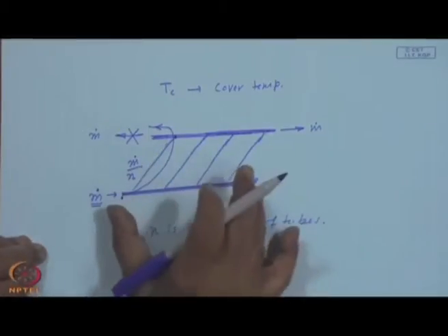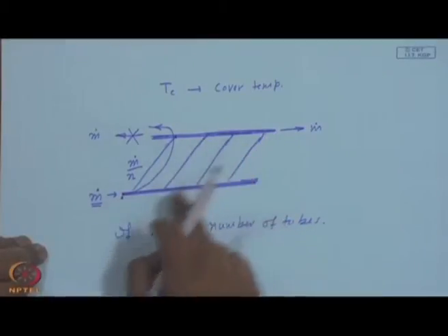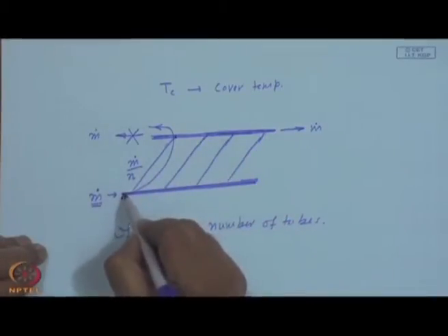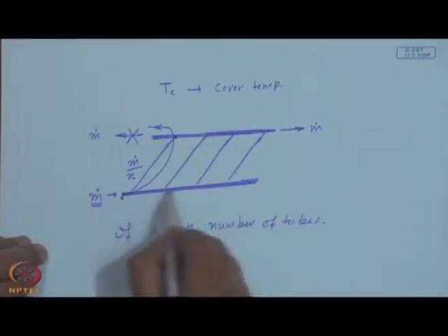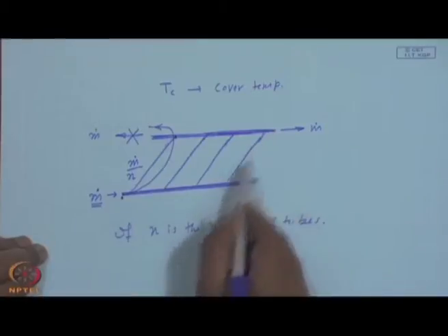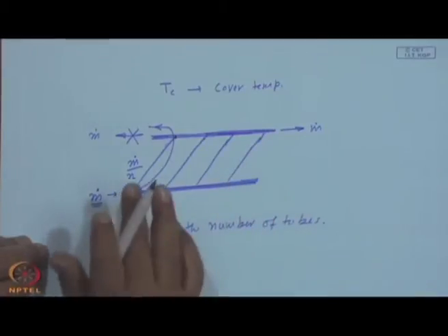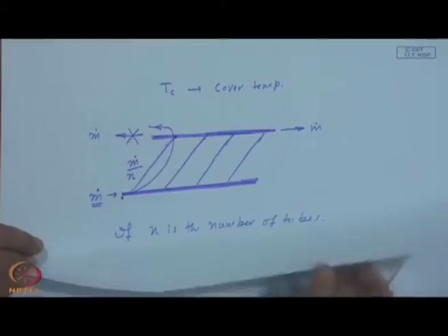In addition to providing a negligible pressure drop, thereby providing a uniform flow, you balance the path length of one tube plus the header and the last tube plus the header. Here is a larger portion. Somehow delta p is more or less the same, trying to provide uniform flow to the tubes.